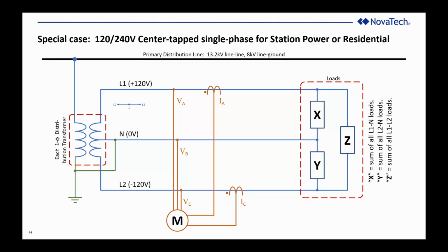You don't typically see somebody using a SCADA meter for residential service, but in a substation, it might be very handy to monitor your station service load using a 2-element wattmeter that's connected to SCADA. So it's a special case, and I think it's interesting because residential kilowatt-hour revenue meters are wired the same way. It's a single-phase wattmeter, but even in a single-phase kilowatt-hour meter, you have to contend with the fact that it's got a center tap grounded neutral and 3 conductors. It's not a single-element wattmeter. You don't use a single-element wattmeter for residential loads. You use a 2-element watt-hour meter to do this.